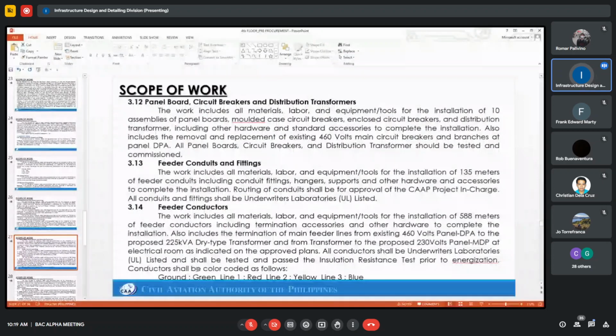Feeder conductors includes all materials, labor, and equipment for the installation of 588 meters of feeder conductors, including termination, accessories, and other hardware to complete the installation. Also includes the termination of main feeder lines from existing 460 volts panel DPA to the proposed 225 kVA dry type transformer, and from transformer to the proposed 230 volts panel MDP at the electrical room, as indicated on the approved plans. All conductors shall be UL listed and shall be tested and pass the insulation resistance test prior to energization.